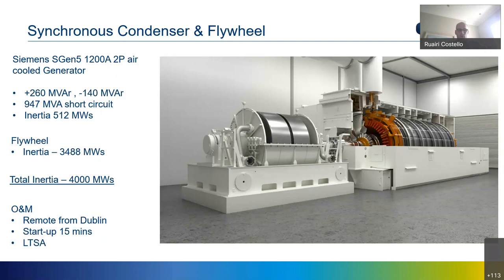And the inertia of the synchronous condenser is 512 megawatt seconds of energy. So we added the flywheel, as I said, to increase the mass. And that brings up the total inertia of the unit to 4,000 megawatt seconds. That would be equivalent to one of our large units, and when I say large in Ireland, it is 400 megawatts. Combined cycle units in Ireland would have a similar inertia.